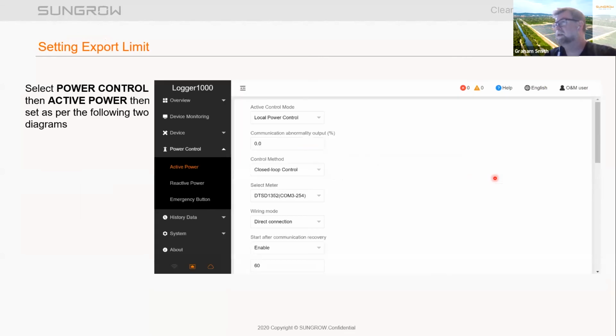Next thing you're going to do is set the export limit, and once again this is very easy. You just select active power control and then active power like that. Oh, hang on, I'll go back one. And once again we'll produce the document.